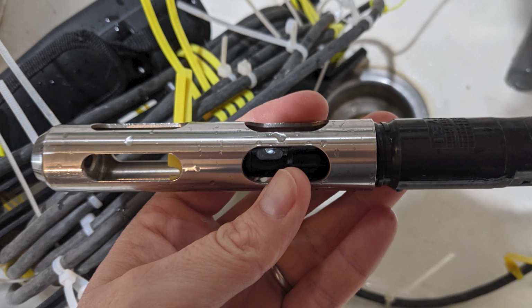First, remove the storage chamber and unscrew the stainless steel guard that protects the DO meter probe so that you can examine the membrane. Every fourth sampling period, you'll also need to remove and replace the membrane. Please check the sampling period calendar that's included in your manual.